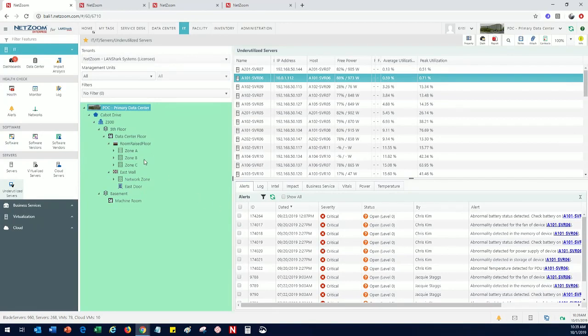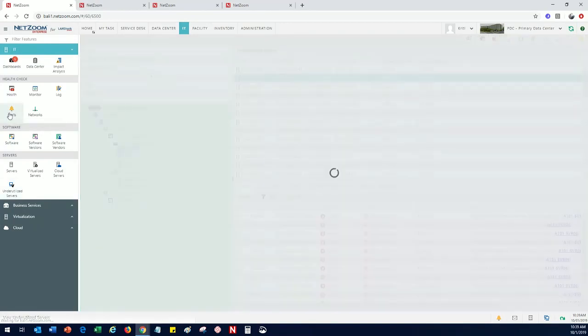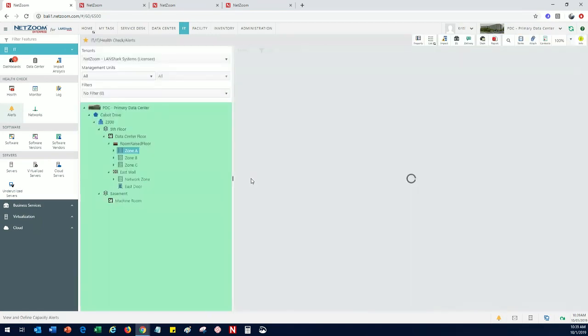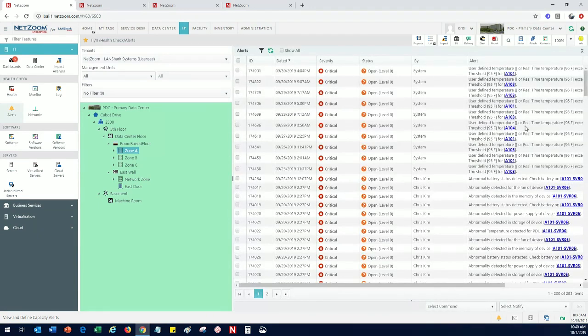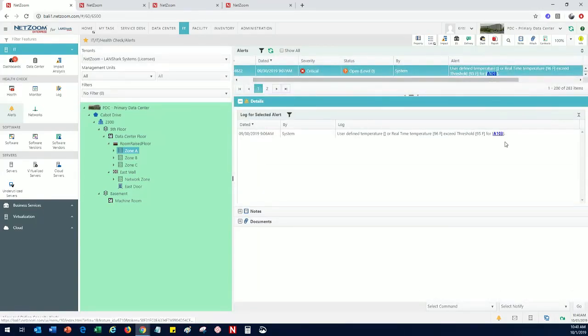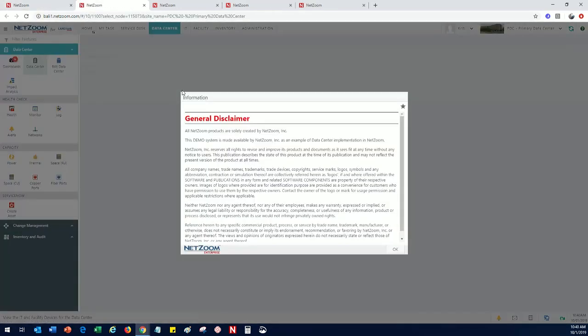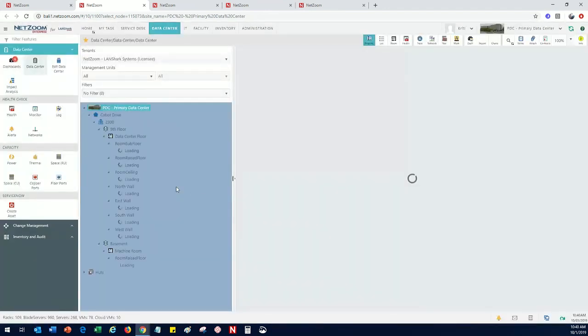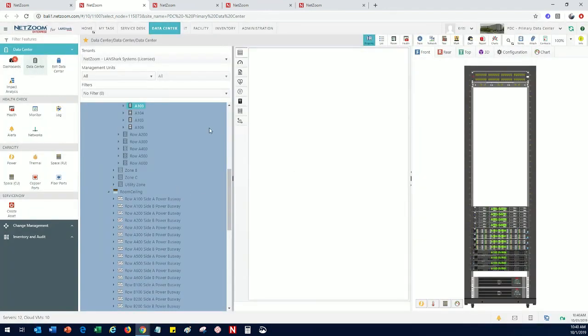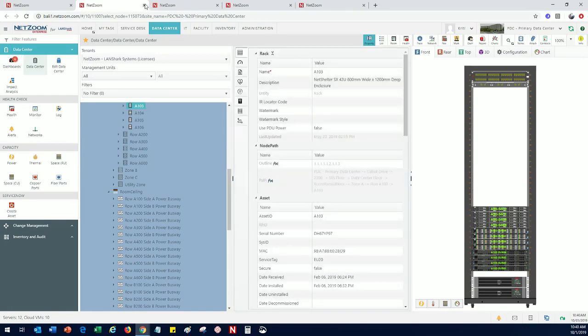Speaking of alerts, we're going to look at the overall alerts for this whole zone. We get real-time monitoring alerts on everything going on in the data center. You can set thresholds for each of your capacities to see what's going to happen, so you can be proactively responding to risks, not reacting to disasters. You see we have a temperature alert here. If we click on it, it brings up the details for the alert, and if we click again, it opens a new tab that drills us straight down to that rack so we can immediately start troubleshooting and find out what's going on.